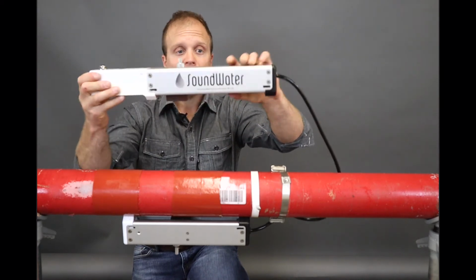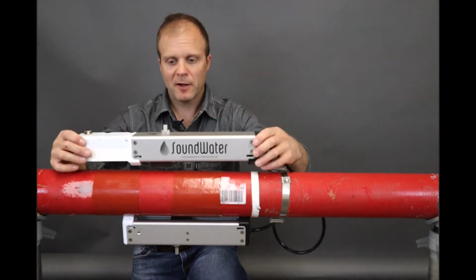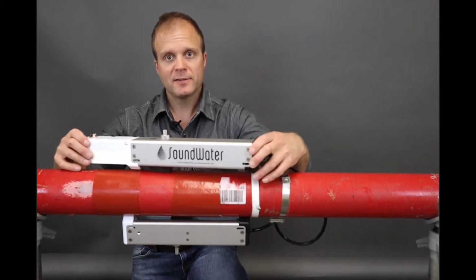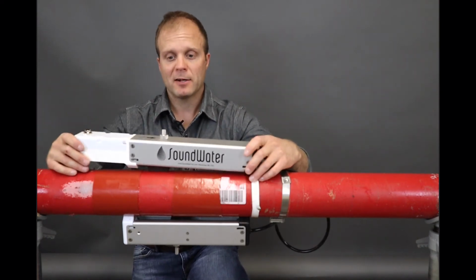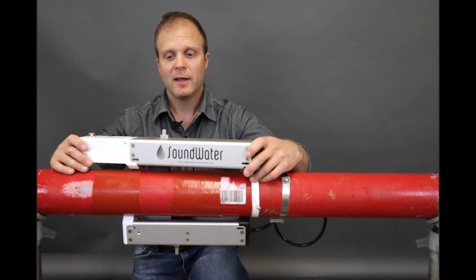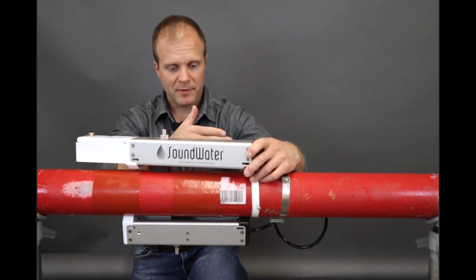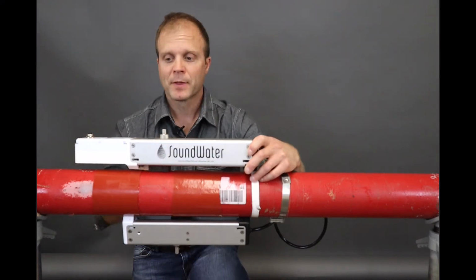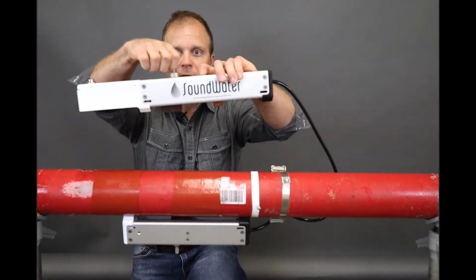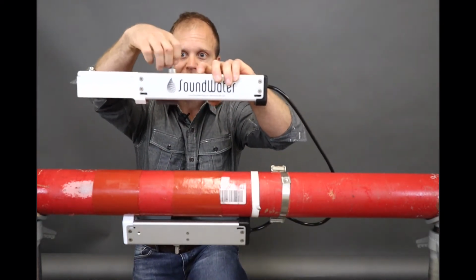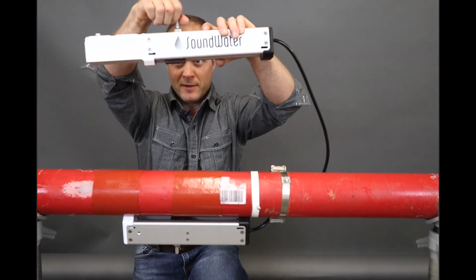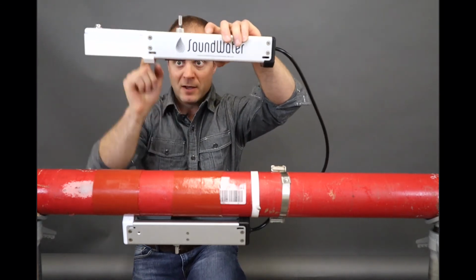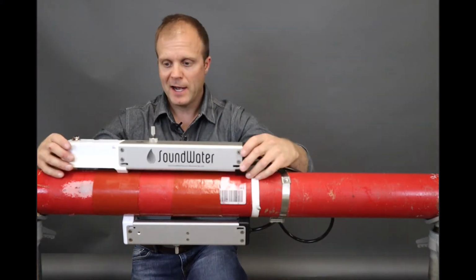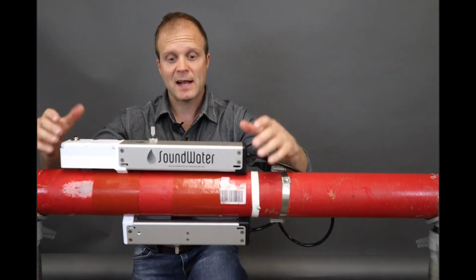And we don't want that because if I put it on the pipe this way, it doesn't axially align with the pipe automatically. So I can install it crooked, and then the sound will shoot in some funny direction and not hit our receiver. Very important, just suck this thing all the way up until it's clearly above each footing here. Now this piece sits nice and axially aligned.